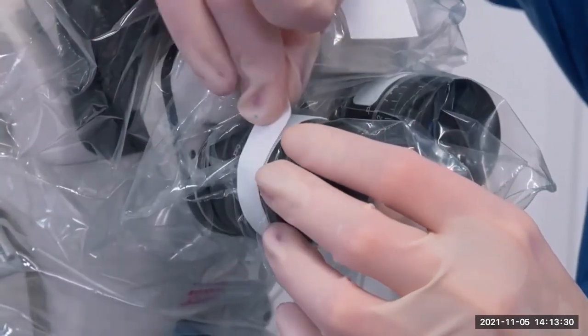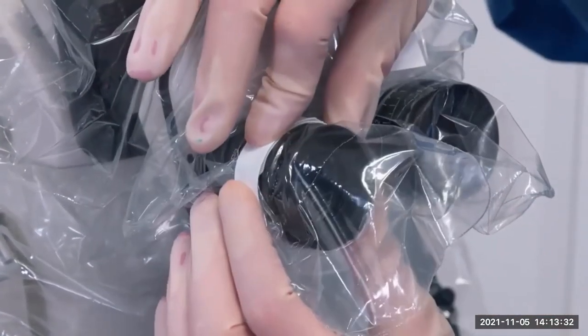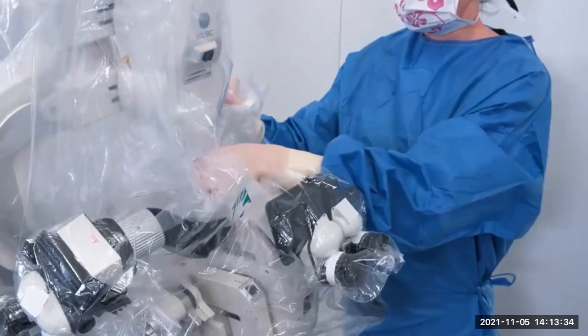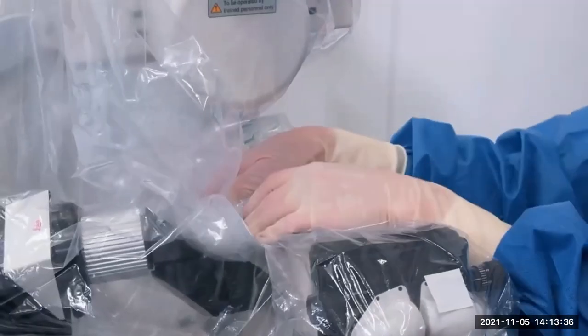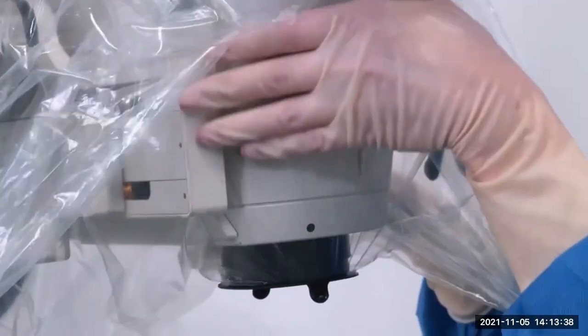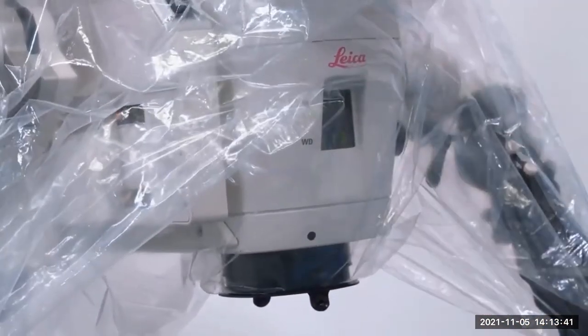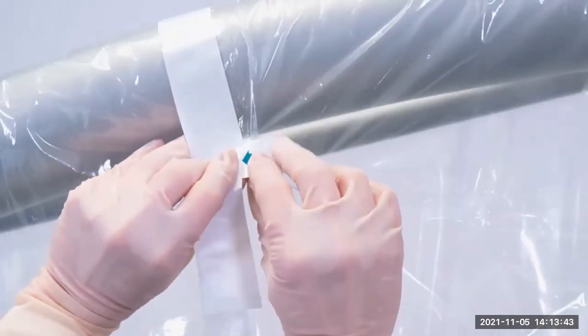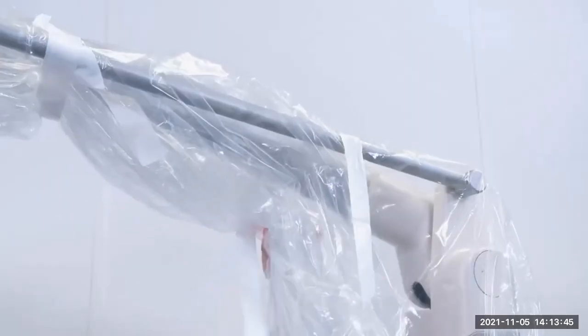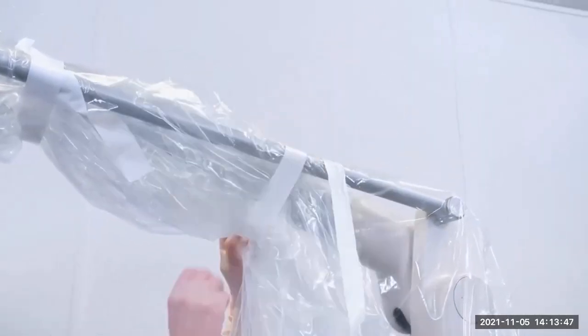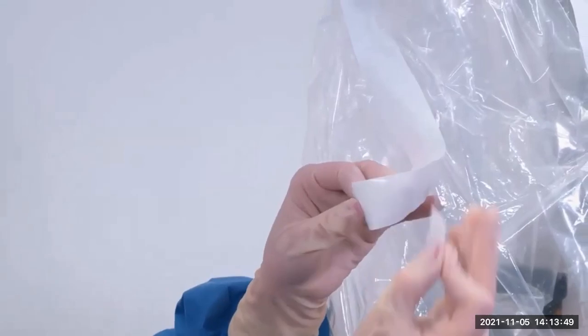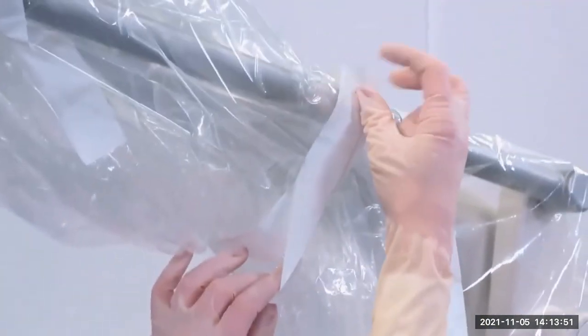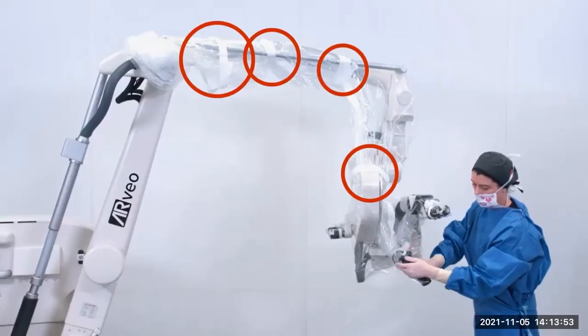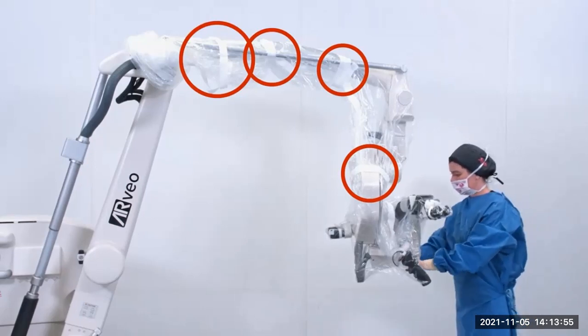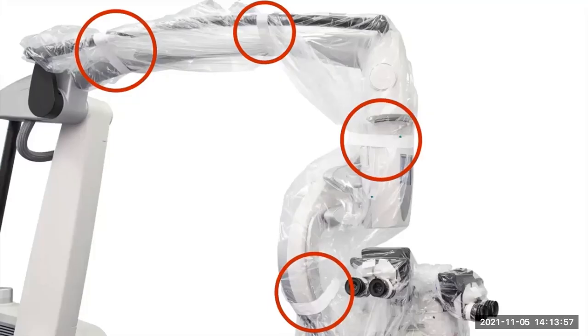Secure the drape using the Velcro straps. Put the remaining drape inside the empty space. Make sure the drape is not covering the lens. Wrap the bands around the microscope head and arm, placing them taped to tape and not taped to plastic, and making sure the drape is fitted airtight to the microscope. Check that the straps are attached around the microscope head and around the arm as shown in the images.